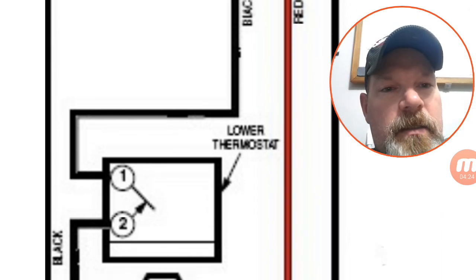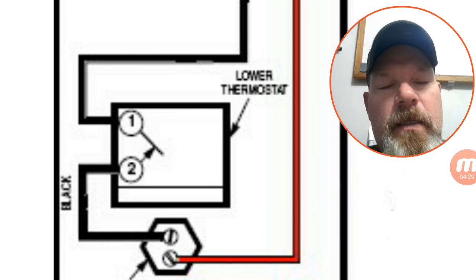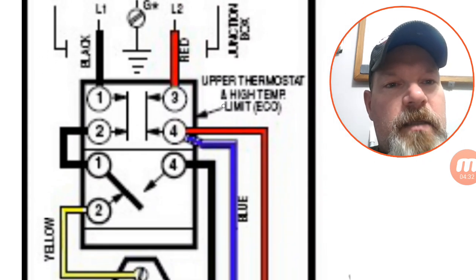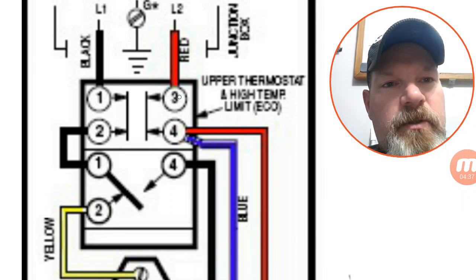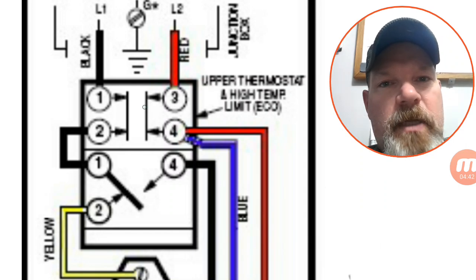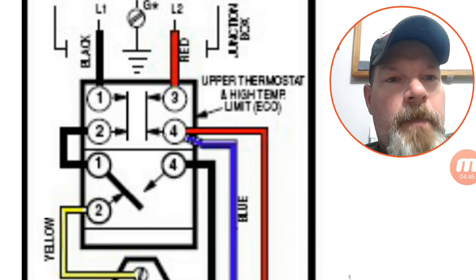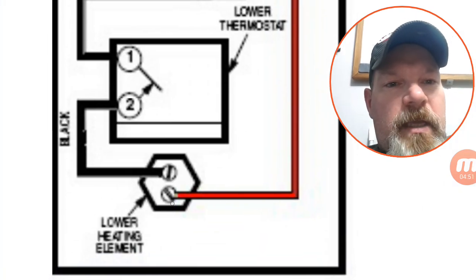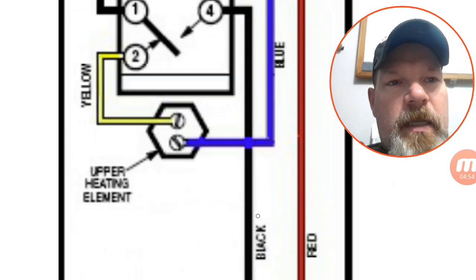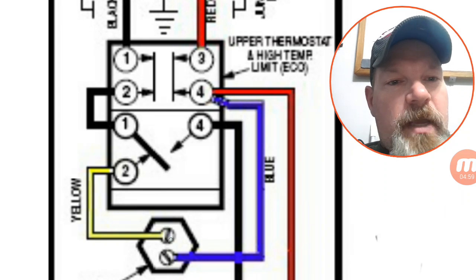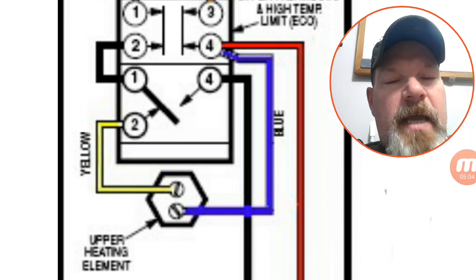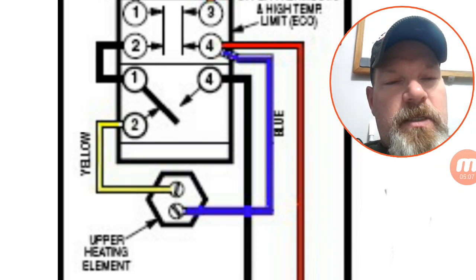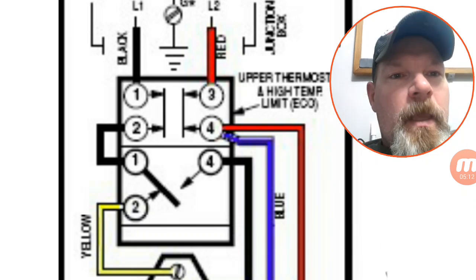And then when the switch closes, it finishes the circuit over to the element. Now real quick, let's run the red through here. This basically does the same thing. L2 comes to number three, goes through that high temperature limit switch, the manual reset, and this side wire just goes all the way down and connects to one side of the lower heating element. And likewise, number four heads over to the other side of the heating element. So that side of things really doesn't do anything, it's just completing the circuit. And all the switching is happening on L1.